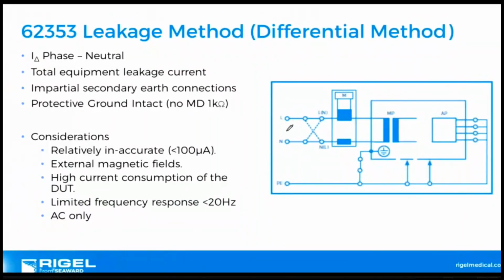62353, the differential method. What happens if we have this scenario that I've gone over time and time again, where we've got 100 milliamps here, we've got 99 here. Where is this non-functional current flowing through? Well, we don't have the body model anymore, and with the differential method, what we're doing is measuring by current coil the difference between the current in the live conductor and the current in the neutral conductor or hot conductor. I should stress for all American guys. Anyway, if we measure this, and this is intact, we don't have the body model anymore. We're just measuring the stray capacitance or distance, how it may be coming down. It's a different type of measurement. So we're not doing Ohm's law. We're not doing it through the body model.